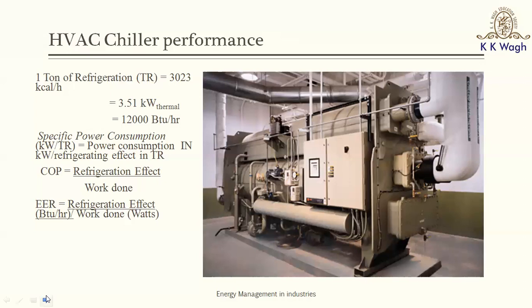In more academic circles, the coefficient of performance is used. COP, or coefficient of performance, in academic circles is referred to as the refrigerating effect upon work done. Similarly, energy efficiency ratio is also the refrigerating effect upon work done. The difference between COP and EER is that in COP, the refrigerating effect and the work done carry the same units, whereas when you are expressing the performance of the chiller in EER, we generally express the refrigerating effect in BTUs per hour and the work done in watts.